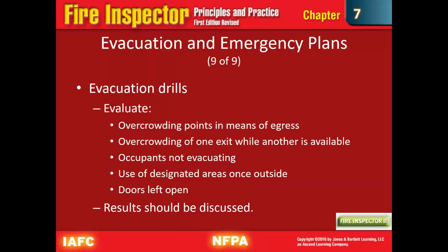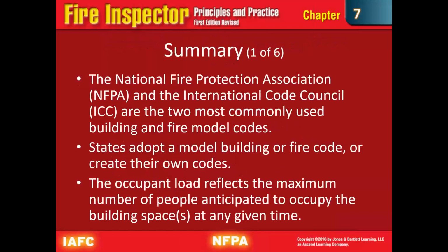It helps, because we never can plan for a very specific issue in a specific area. We can check for occupants not evacuating, the use of designated areas once outside, and any doors that are left open. Then, if we evaluate these fire drills, we need to discuss it in a good, constructive way, so that the information is taken and used to develop the drill better.